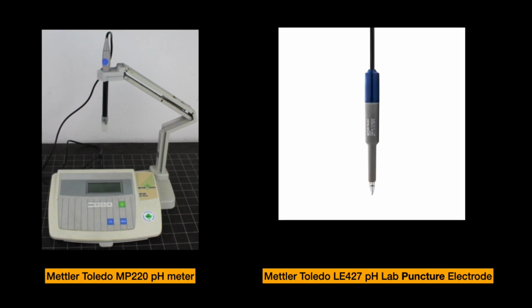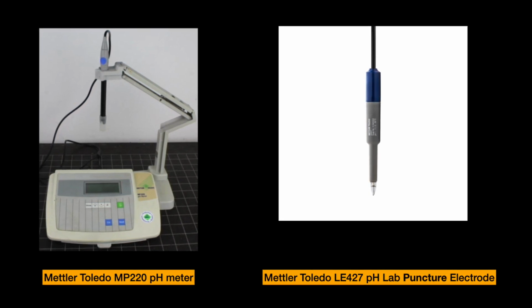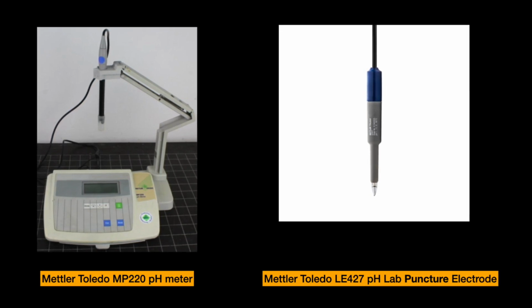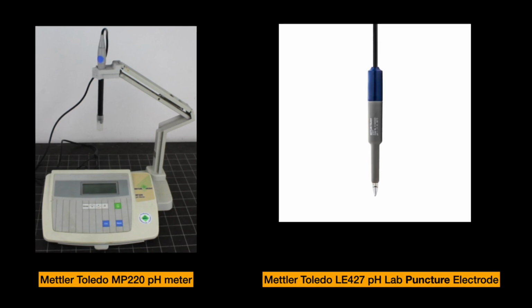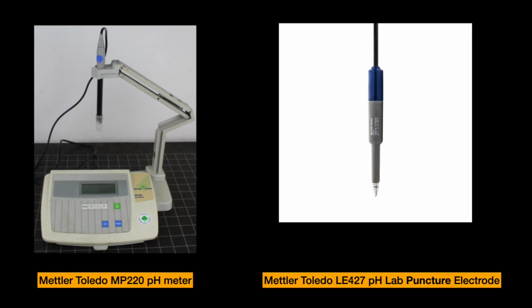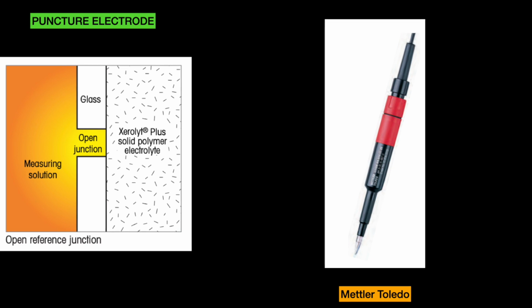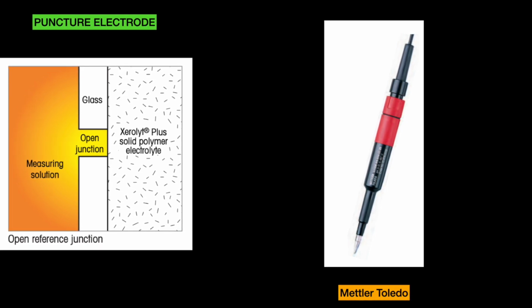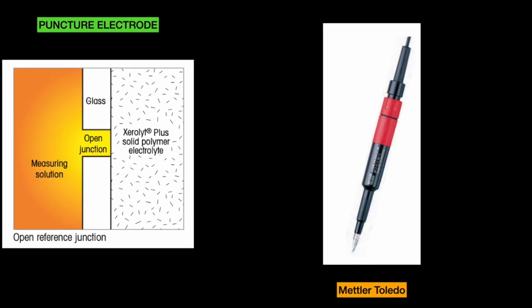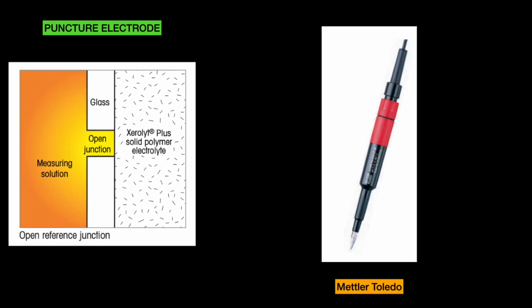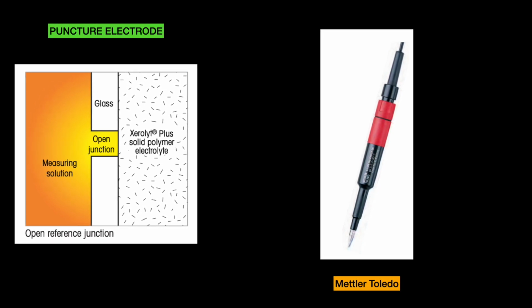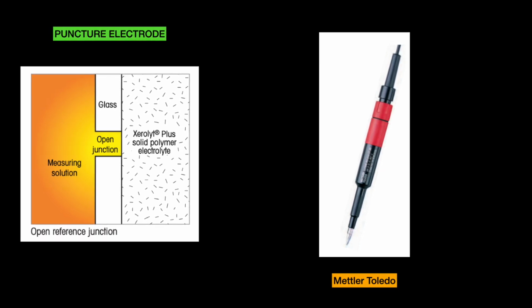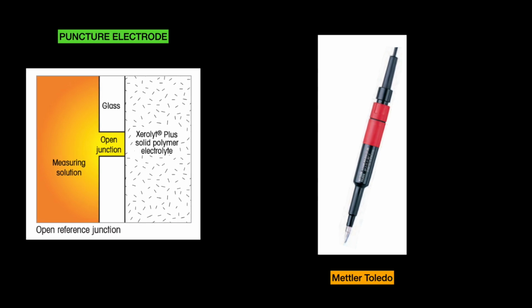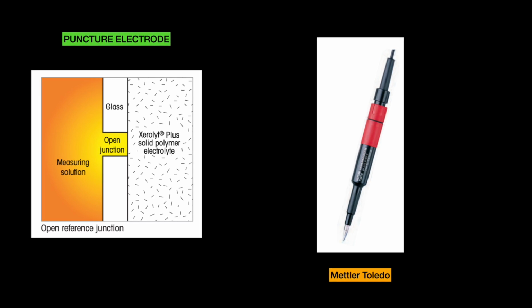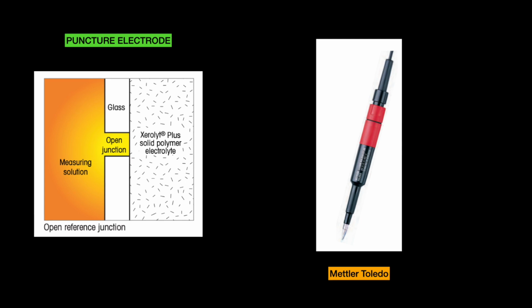There are special electrodes for this, like spear tip electrodes, for example, shown here on the right. They are also called puncture electrodes. They are designed for semi-solid samples like food, cheese, meat, or gels. This one, for example, has a protective plastic cover around the glass shaft. Now, this electrode is sealed, it is non-refillable, and what is special about this electrode is its reference system is solid polymer separated from the measuring solution using this open junction design. And this means the system would not get clogged up by fat and proteins.